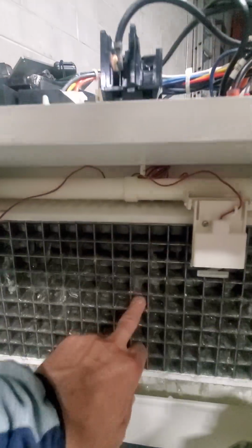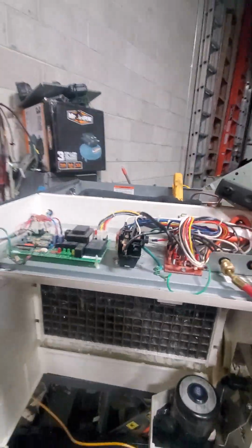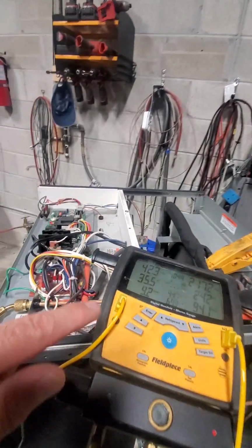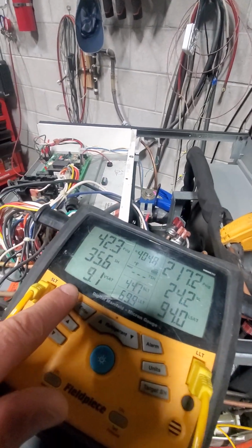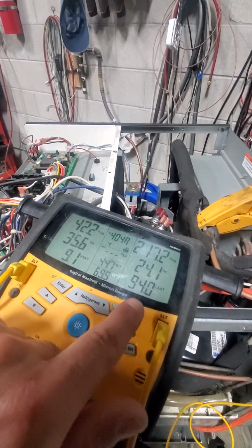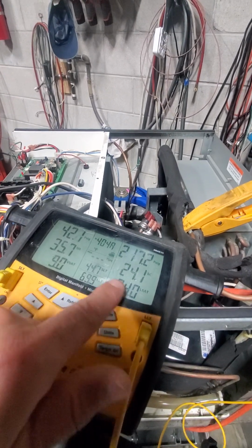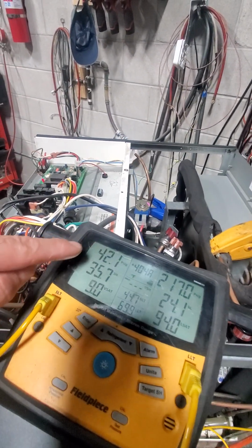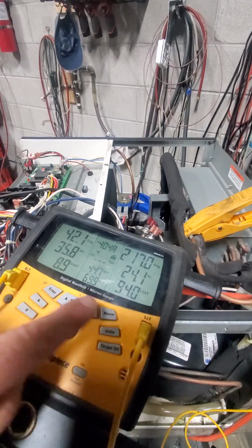So as I was showing you earlier, you see this is really, really cold. And if you have the gauges on, it will tell you the actual temperature of the evaporator, the actual temperature of the condenser, the pressure—high pressure, low pressure, superheat, subcooling. So this is the temperature here.